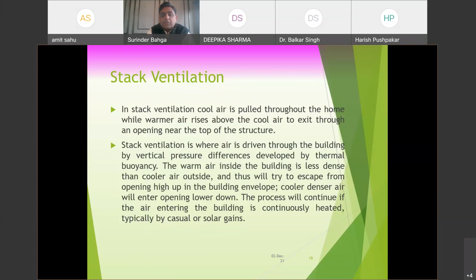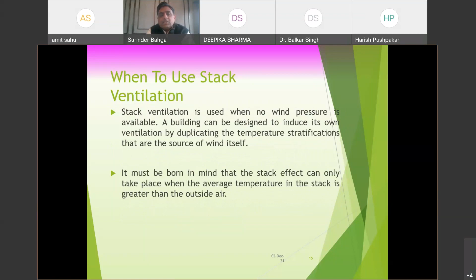Stack ventilation is where air is driven through the building by vertical pressure differences developed by thermal buoyancy. The warm air inside the building is less dense than cooler air outside, and thus tries to escape from the high opening, which I explained earlier. When to use stack ventilation: when no wind pressure is available, a building can be designed to induce its own ventilation by duplicating the temperature stratification. So these are a few aspects which have to be clubbed into the architecture, on how to use stack ventilation.